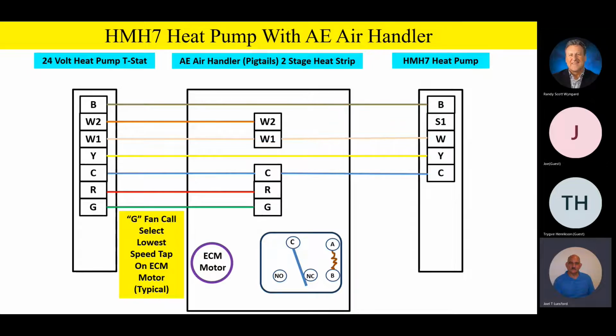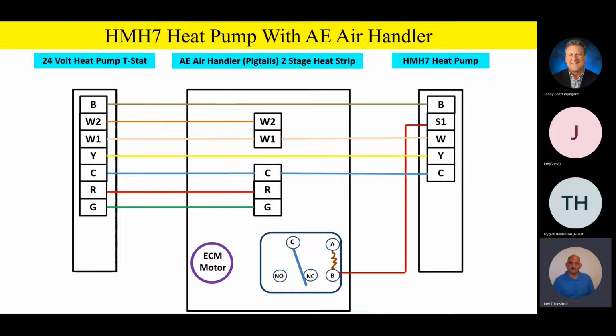And so let's talk about how we're going to hook that up. What we're going to do, one side of the relay coil, that's a 24-volt coil, we're showing B terminal, is going to go up and hook to a wire on the outdoor unit called S1. That S1 is a 24-volt output from the outdoor unit to B terminal, or one side of the relay coil, and that's going to energize that coil.